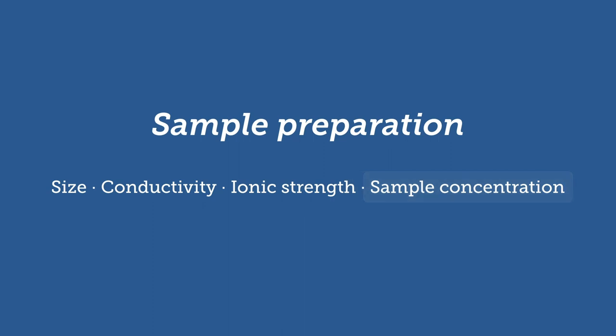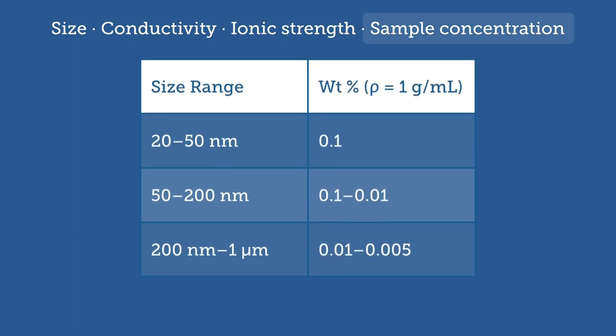According to Malvern, the Zetasizer Nano can detect particles with diameters between 3.8 nanometers and 100 microns for zeta potential analysis. There is a very strong relationship between the diameter of a particle and the intensity of light scattered from it, so concentration requirements will vary. This table provided by Malvern shows the recommended sample concentrations for different size ranges. Note that the table is modeled after polystyrene latex, which has a density of around one gram per cubic centimeter, so your sample needs may vary proportionally.